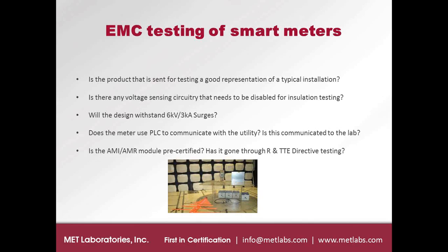Is the AMI/AMR module pre-certified, and has it gone through RED directive testing? Any radio modules that you're integrating into your product, you want to make sure that they are already pre-certified. Now you would think that since you're testing your product against ANSI for the US market, all you need to make sure is that the product is certified for FCC Part 15 for intentional radiators. But it does make sense to verify that your AMI/AMR module is also designed to meet the European requirements, and that it meets the RED directive testing, wherein the product goes through the EMC test for the intentional radiator. So it will give you a lot of confidence when performing tests like fast transients or surges to a limited capability, or ESD and other such tests.